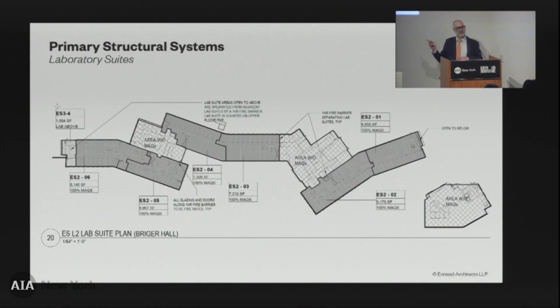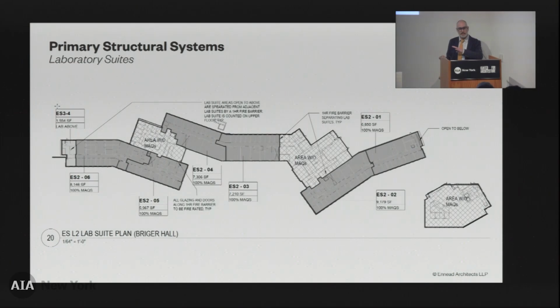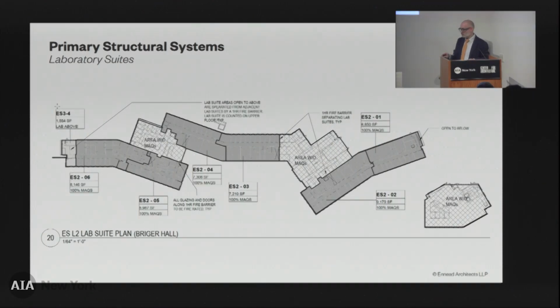This may be of interest to those who work in laboratory projects: the term laboratory suites. Depending on jurisdiction it can be defined differently, but for New Jersey this was filed under the 2018 IBC New Jersey edition. A laboratory suite can contain more than just a laboratory, it can contain offices, workstations, bathrooms, whatever you need, as long as it's separated from adjacent construction by a 1-hour fire barrier, and the floor slab is 2 hour. Remember I mentioned that zone of timber being 2 hour? This laboratory suite contains both steel and timber, so it was critical and required that this timber be 2 hour rated.